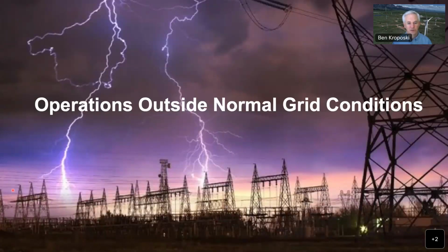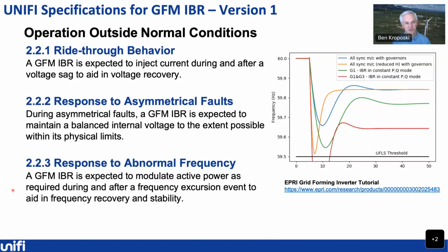Okay, so as we look away from normal to abnormal conditions, so fault type conditions, we want to ensure that these technologies have proper ride-through behavior. So examples of that you can see over here in this particular figure. If you're at 60 hertz and you experience some type of event, then if you have too far of a frequency fall, you may dip below an under frequency load shedding threshold that may start to drop load.